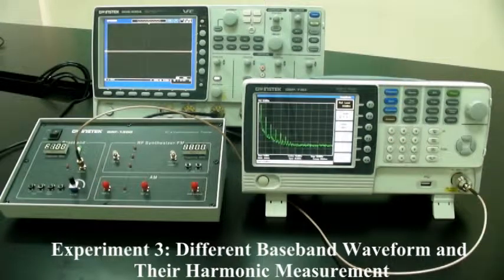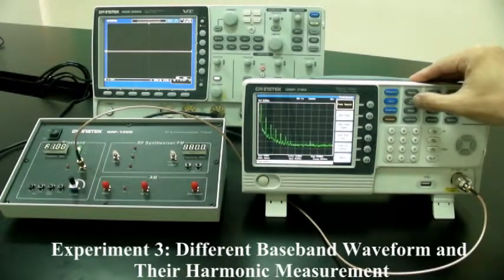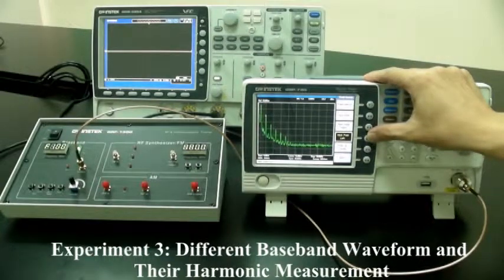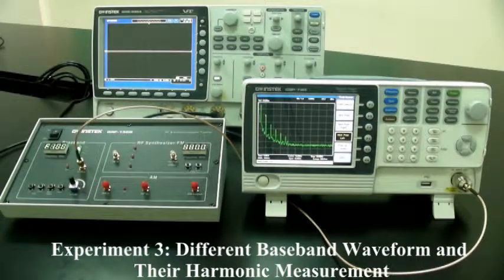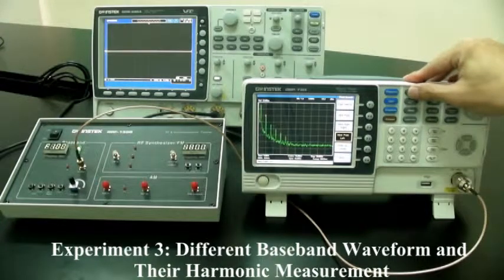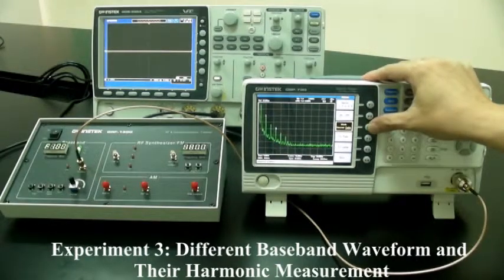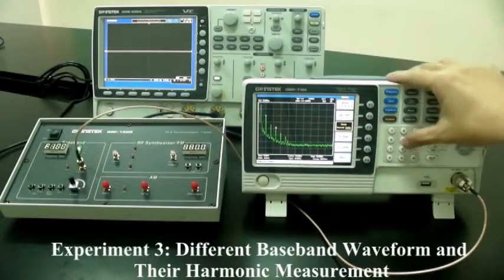Observe the spectrum that appears. Use the marker function on the spectrum analyzer to determine the harmonic ratio. Set marker to 2 MHz. Mode: Delta. Enter.